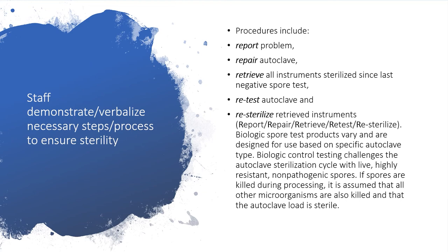When re-sterilization occurs, follow the same standards as original sterilization parameters, such as correct packaging, and document on your load-run log. Label packages and store instruments in a separate, clean, dry-labeled area such as a cabinet or a drawer.